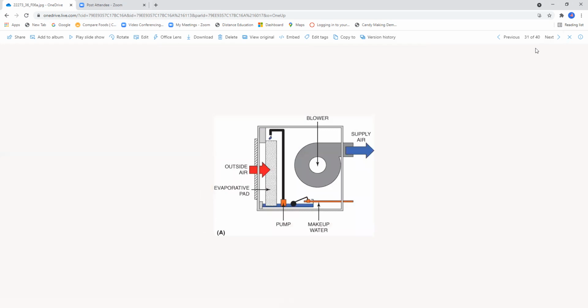Okay, in this illustration here, it looks like a swamp cooler. This is how a swamp cooler works, or an evaporative condenser, evaporative cooling. It's very simple in nature. The downside of this type of cooling is simply the fact that you're going to have a lot of maintenance involved here. Now, this particular picture is going to be on page 1064 under 36.6.